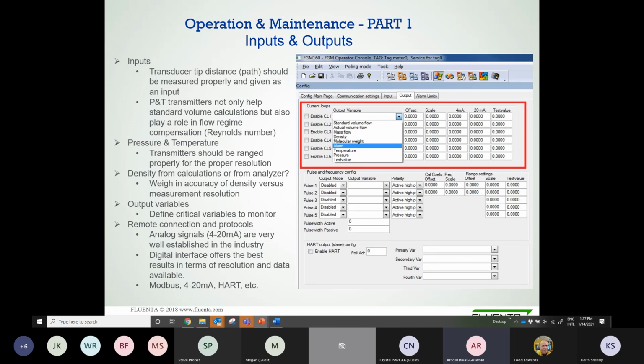And when it comes to the inputs, it's fairly simple. The flow computer needs an input from the transducers, but we also have pressure and temperature measurements on the line, and we take those measurements as an input for our calculations. Now, when it comes to outputs, we can focus on the list we have here. We can show the standard volumetric flow, the actual volumetric flow, mass flow rate, density, molecular weight. We can set up alarms in case you want to set it up for an emergency situation or maybe an overpressure situation. Same with temperature, in case you want to handle things like dew points for condensation. And we're monitoring that. So we have different outputs.